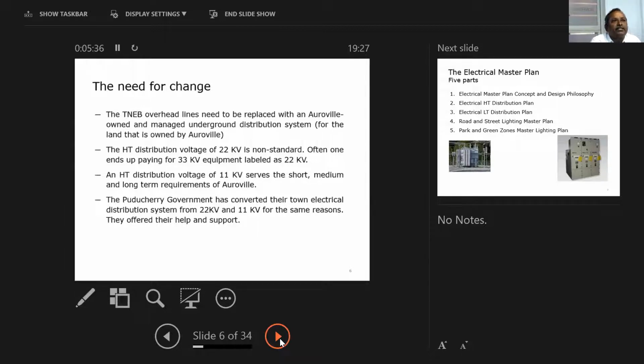Actually, the sample, we can see in Pondicherry. They have shifted from 22 kV to 11 kV recently. And the whole of Pondicherry, I think, is working with 11 kV instead of 22 kV, because 22 kV supply is a non-standard voltage. Actually, we were paying much more. Till now, we are paying very high for buying the transformers and equipment, because it is 33 kV system equipment, so we are paying much higher.